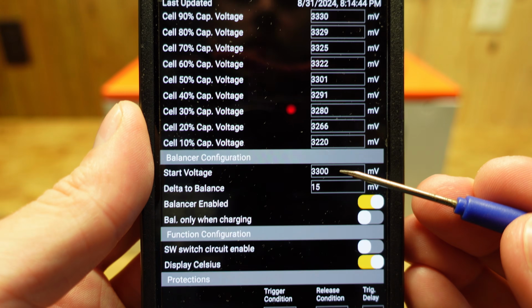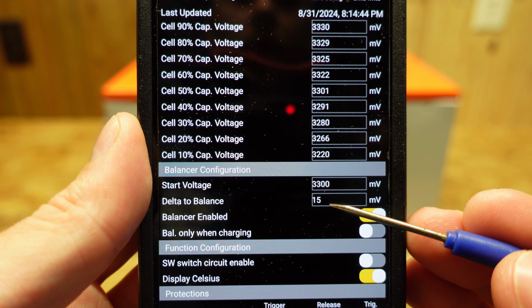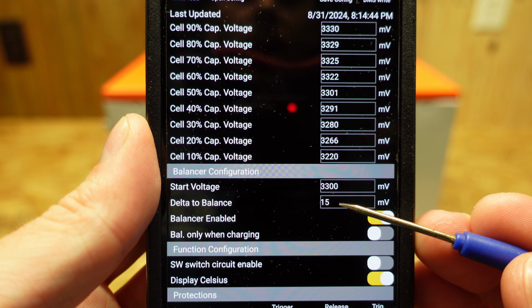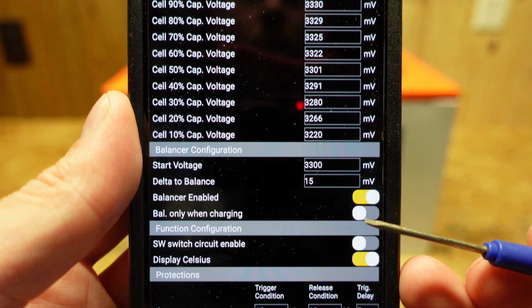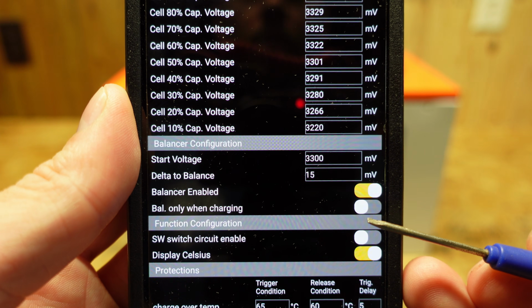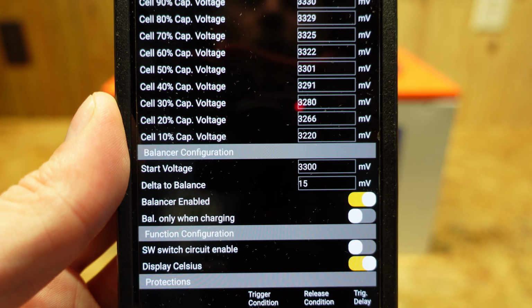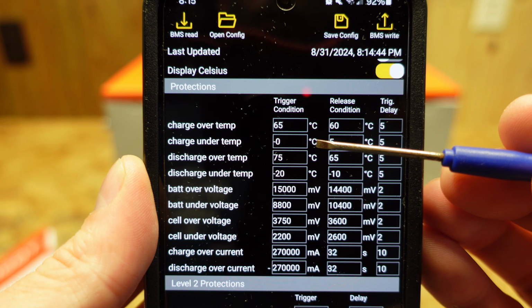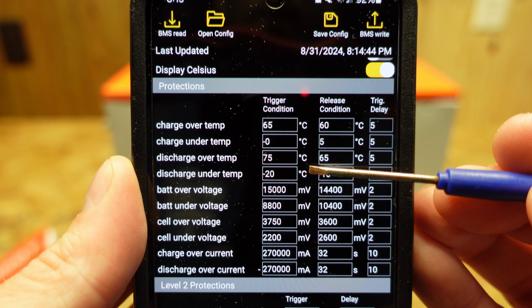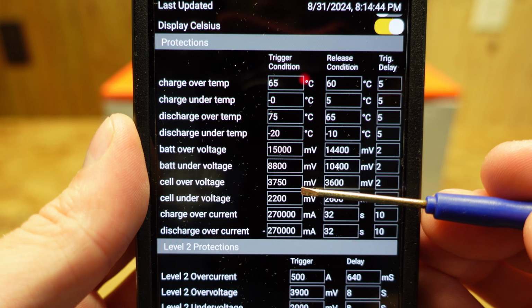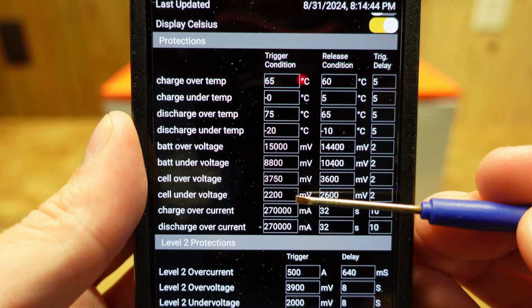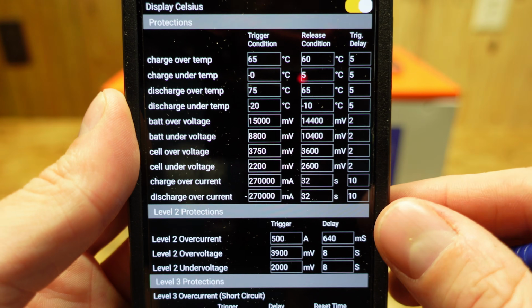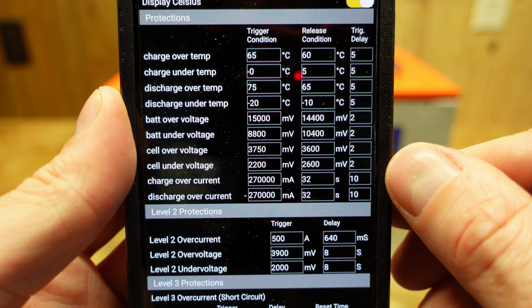It's programmed to balance at 3.3 volts when there's a differential of 15 millivolts between cells. And the balance when charging switch is off. That's good, that means it'll balance all the time, not just when there's a charger connected. So low temperature charge protection is set for 0 degrees Celsius. Over voltage is set for 3.75 volts and under voltage is set for 2.2 volts. So I'm perfectly satisfied with all of the parameters I am seeing here.